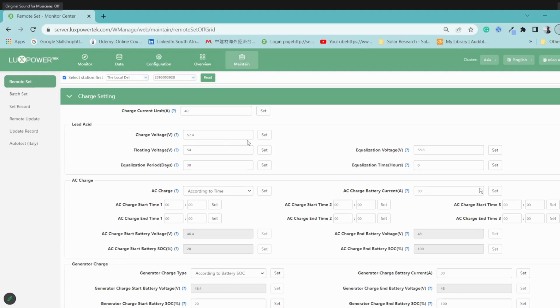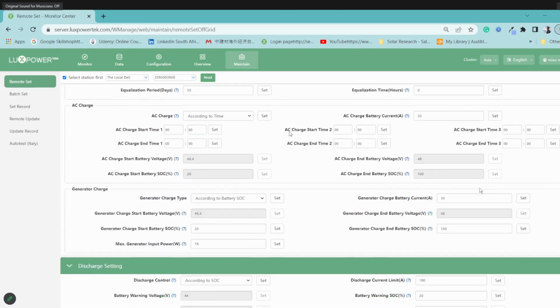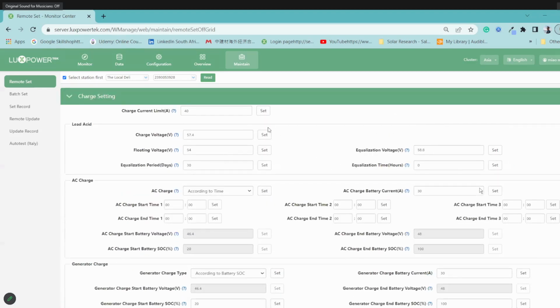If you need some information for the batteries, you can contact us. Most batteries have information and I'll provide it to you. So with your Hubble battery, sometimes the BMS does not want to communicate with the inverter, and sometimes you need to update the BMS on the Hubble battery. I believe this support is pretty good. So what we'll do is I have information, I'll help you temporarily program it as lead acid so the system is working and the client has power.